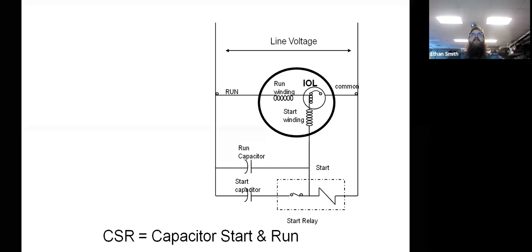So you'll see this on motors that have high starting torque. You'll see this a lot on air compressors. You'll also see this on air conditioning compressors, especially in the age of non-bleed TXVs, where we anticipate starting under pressure and against a load. And this is what's called a potential relay right here in the dotted box. What this does is this relay has a little coil of wire right here. It's just like a normal relay, but that relay is wired in parallel with the start winding. And you can see that here where we pick up common on one side, we go through the coil of the relay, and we pick up start on the other side.